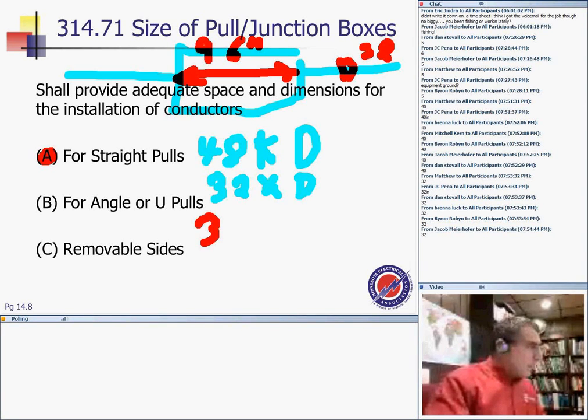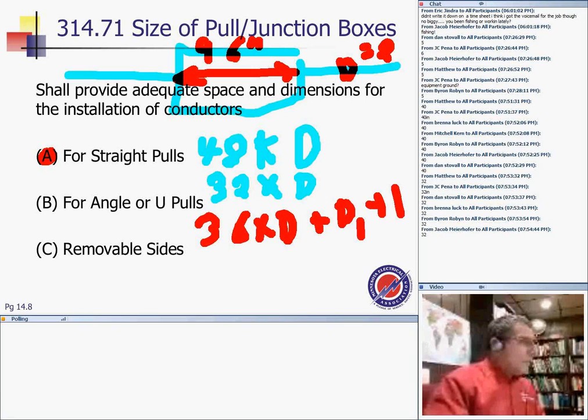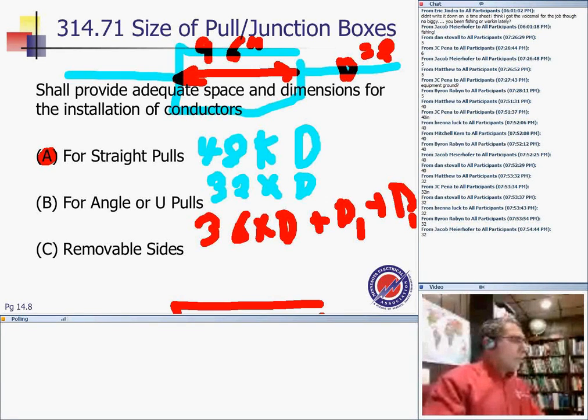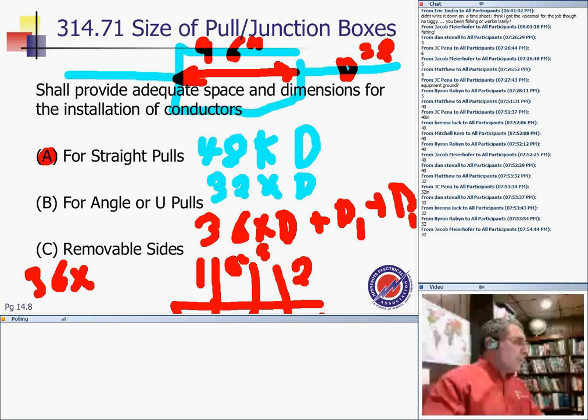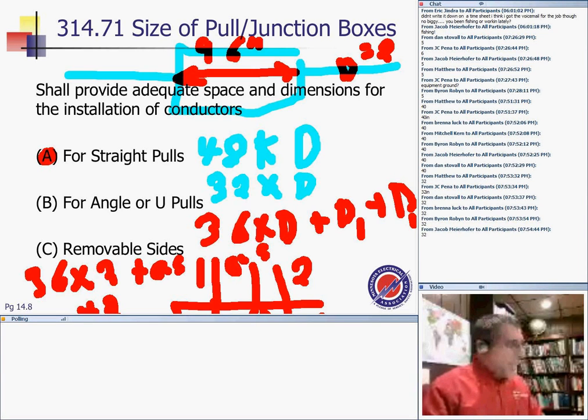36 times the diameter plus other diameters. Diameter 1, diameter 2, the other diameter. So cable 1 coming, leaving, cable 2 coming, leaving, cable 3 coming, leaving. So let's say this was 1 inch, this was half an inch, this was 2 inch. So 36 times 2 is 72, plus half, plus 1. So 74 and a half. So then the box from here will be 74 and a half inches. These are big boxes, guys.